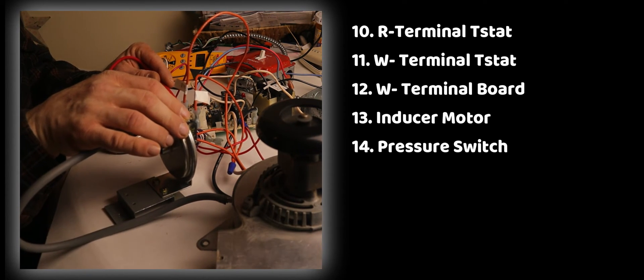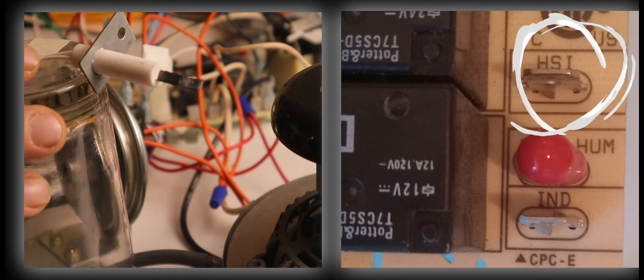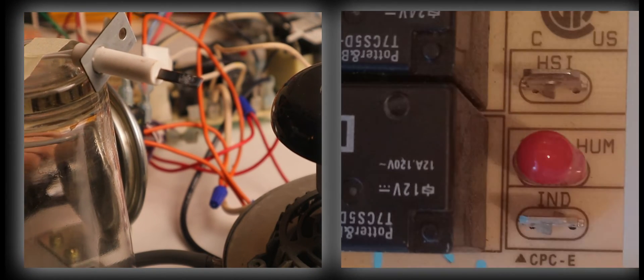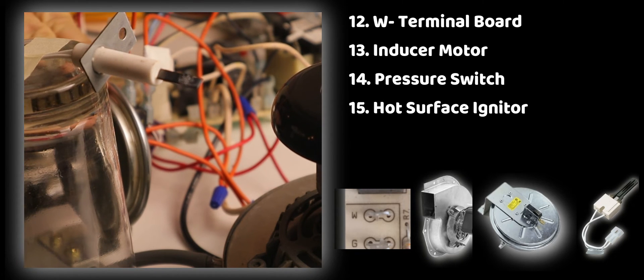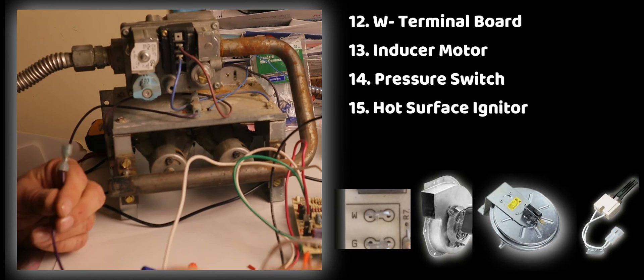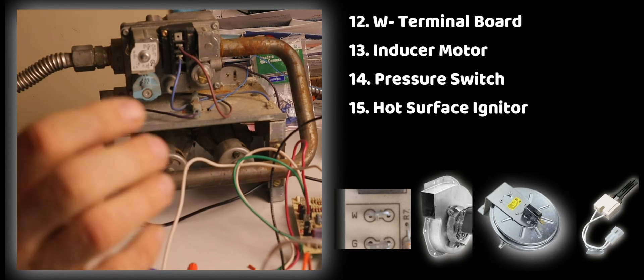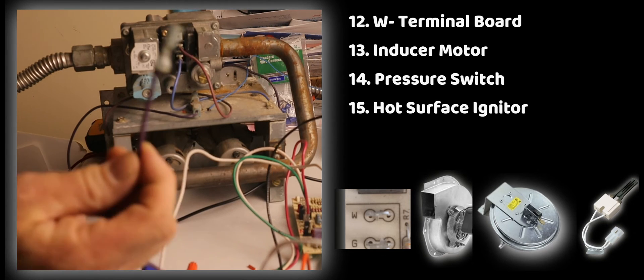Now we have power on our hot surface igniter. The hot surface igniter is now plugged into the board. I'm going to turn heat on at the thermostat again. The inducer motor comes on, our pressure switch is made, and we have power on our hot surface igniter and we should start to see that glow. There we go. When our hot surface igniter lit up there was a little bit of a time delay to allow the igniter to get hot enough.